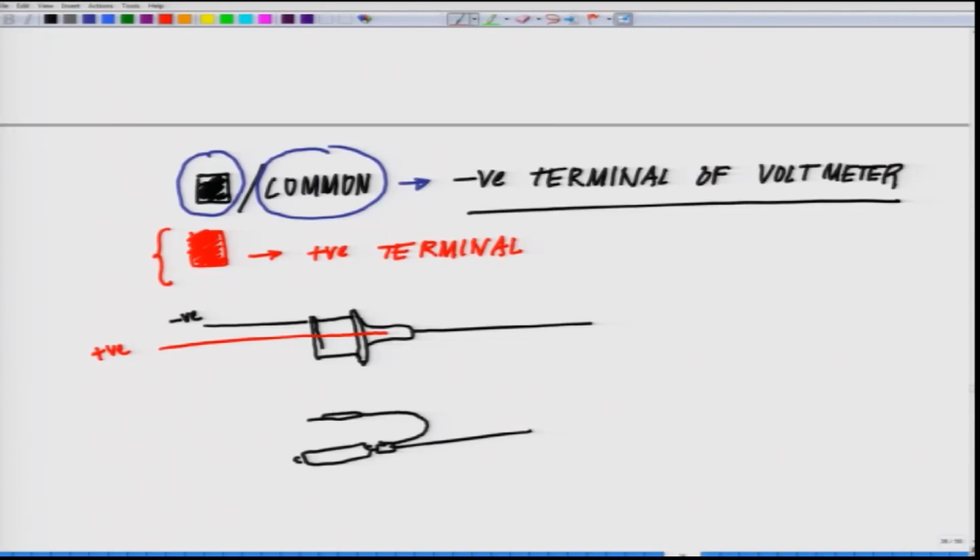Okay. Similarly, if you look at these older style ones, which you mostly see in devices imported from the US, you will observe there is an additional thin connector. On these pH meters, this is called the reference, or negative terminal, and the pH is on the positive terminal.